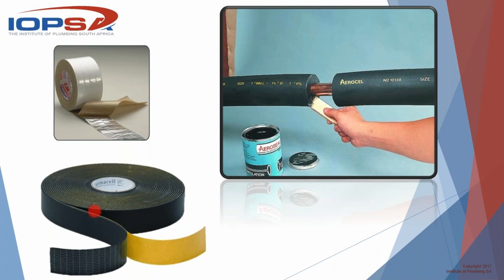Then you get products like this. This is a tape which is made out of the same material as this. It comes as a self-adhesive tape with a backing. You peel it off and wind the tape around either a butt joint, or perhaps in a tricky situation like a valve, where you've got an odd shape that a tube won't be able to lag. You can wind it around 5 or 6 times to build up that thickness, and you essentially are lagging the thing perfectly well with this tape. It's sticky, it's self-adhesive, it doesn't come off.